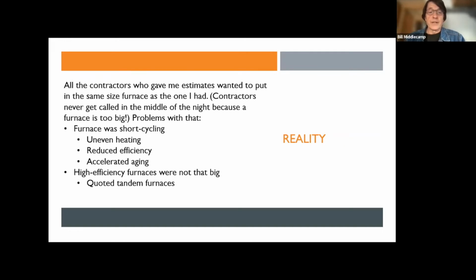All the contractors gave me estimates to put in the same size furnace for one big reason, that contractors never get called in the middle of the night because a furnace is too big. But the problem with that was my furnace had been short cycling. I actually have 3-zone heating. And so it would turn on to heat just one floor. It would complete that in about 5 minutes, and then it would shut down. So you get these bursts of heat, and then it would cool down. It was uneven. I don't think it was very efficient running that way.